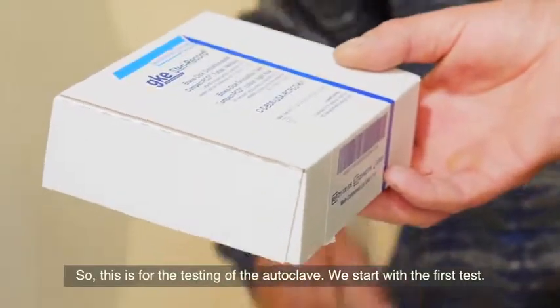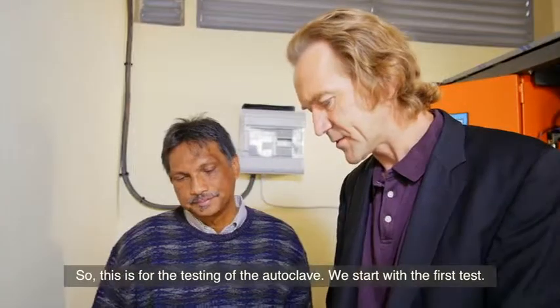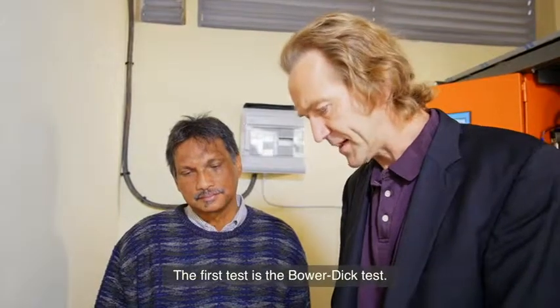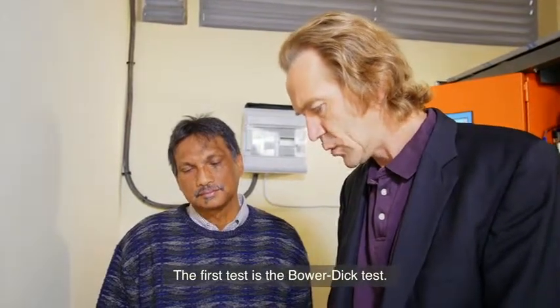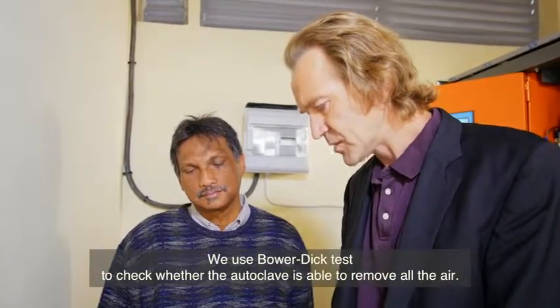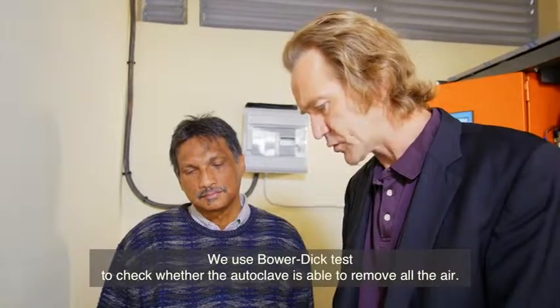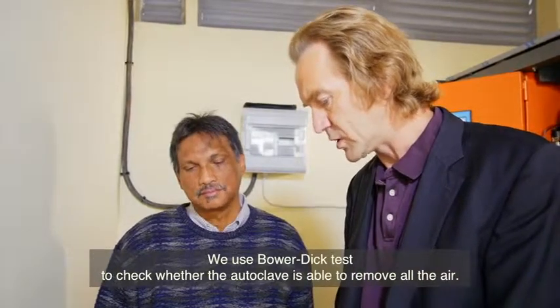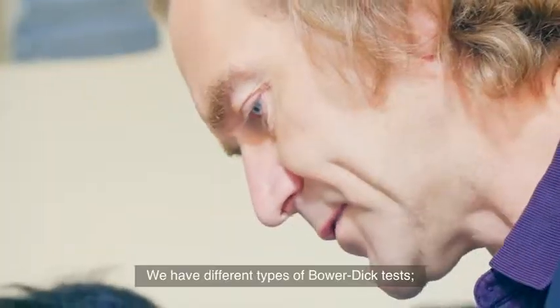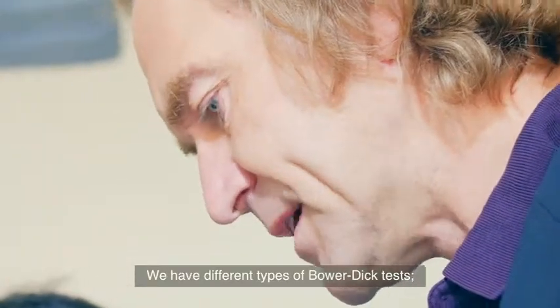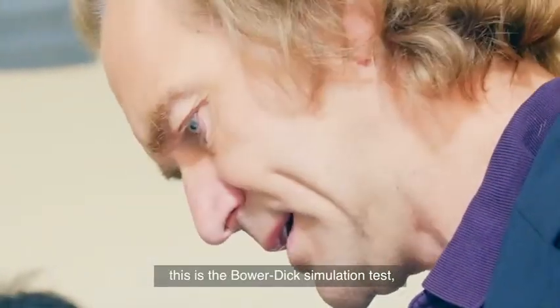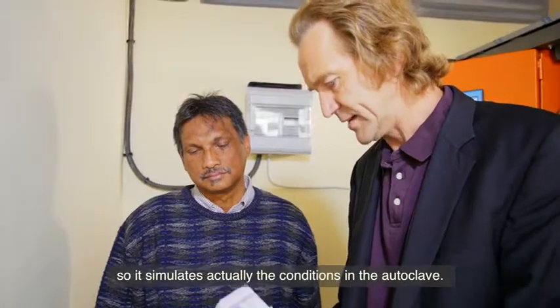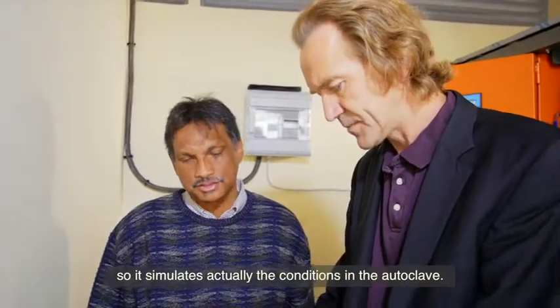So this is for the testing of the autoclave. We start with the first test. The first test is the Bowie-Dick test. We use the Bowie-Dick test to check whether the autoclave is able to remove all the air. We have different types of Bowie-Dick test. This is the Bowie-Dick simulation test. So it actually simulates the conditions in the autoclave.